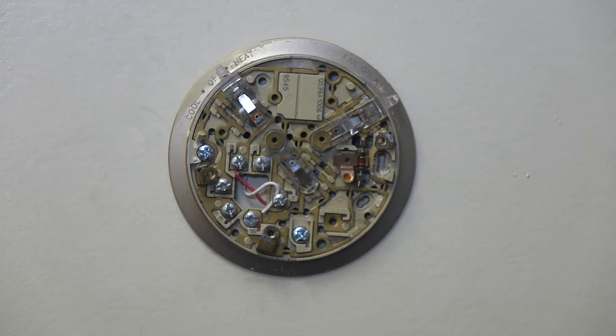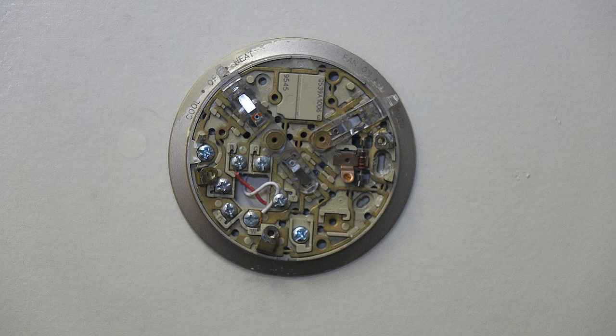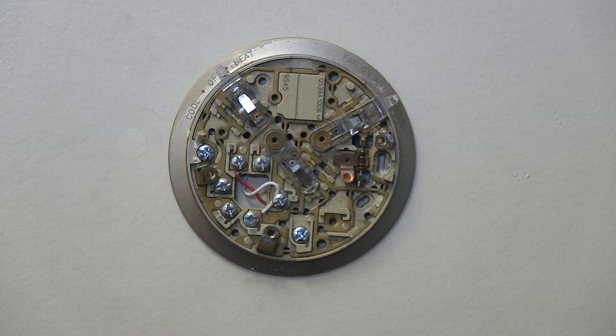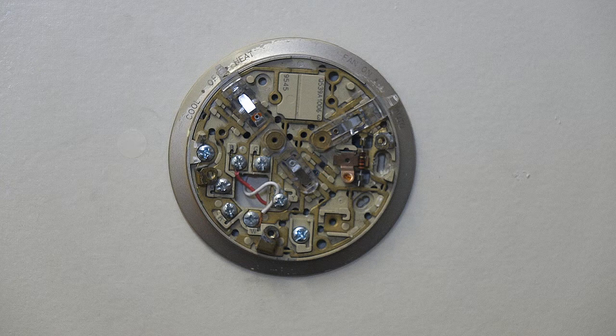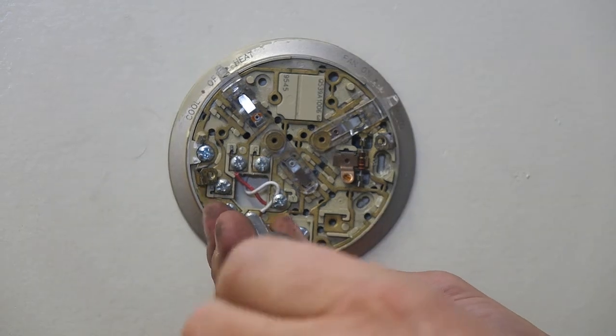Once we remove the main plate, you will notice we have two wires connected to the thermostat. In this example, we have a red wire going to the R terminal and a white wire going to the W terminal. Your color scheme may differ, so just make a note of what color scheme you have. Let's remove those from the thermostat.